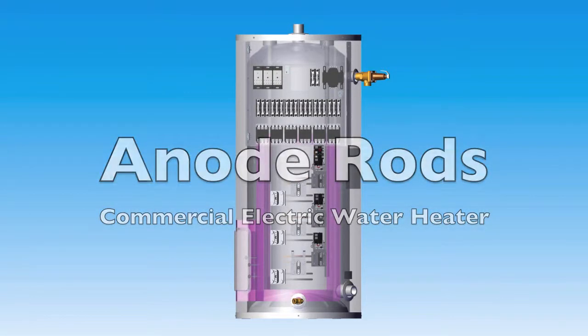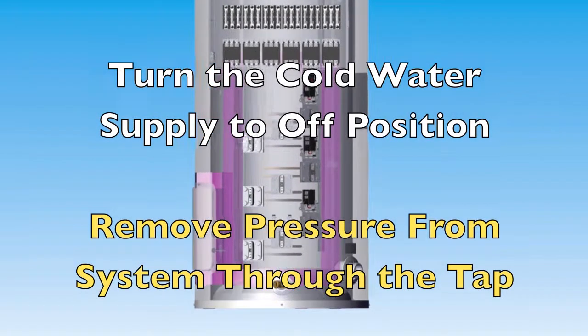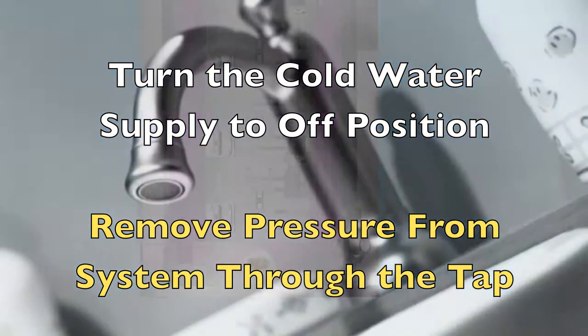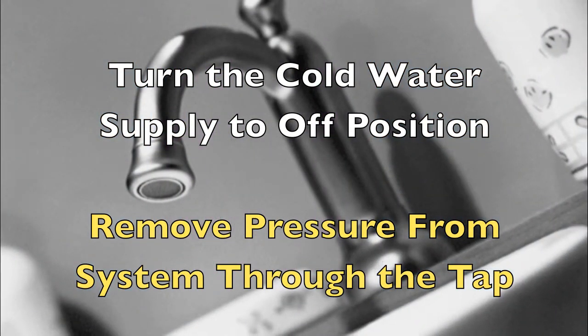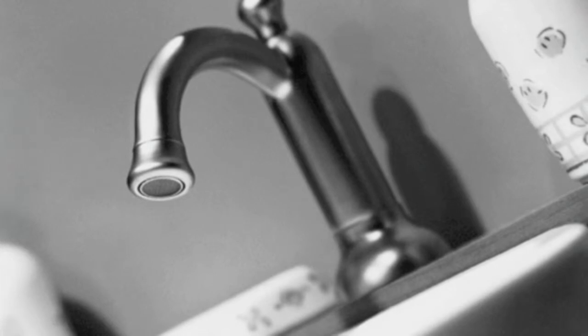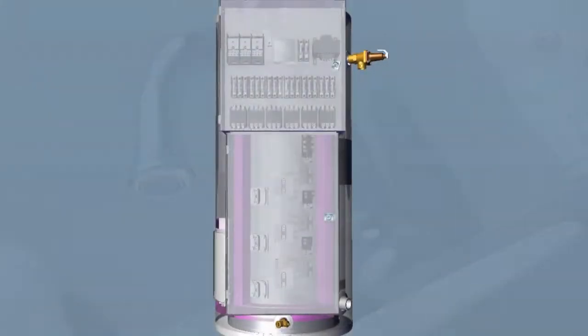Anode rod. It is very important to turn cold water supply to the off position and remove pressure from system either through the drain located on the cold inlet or through a domestic tap before anode rods can be removed.